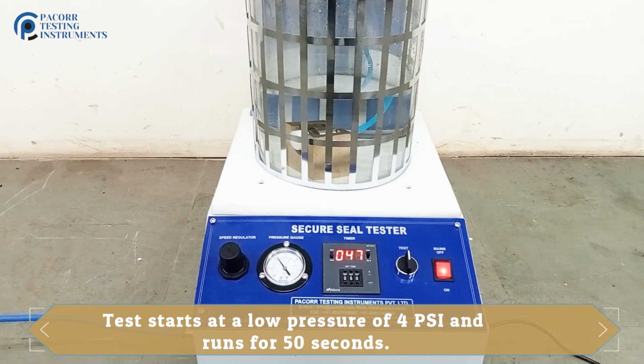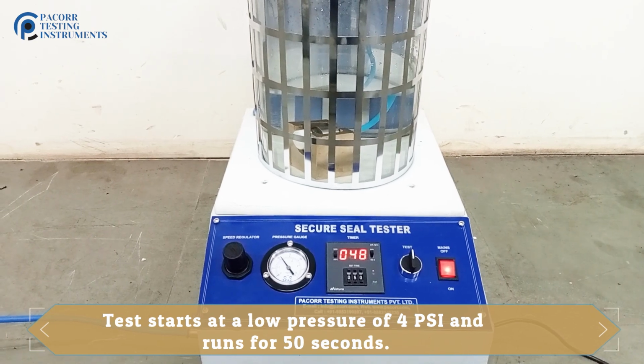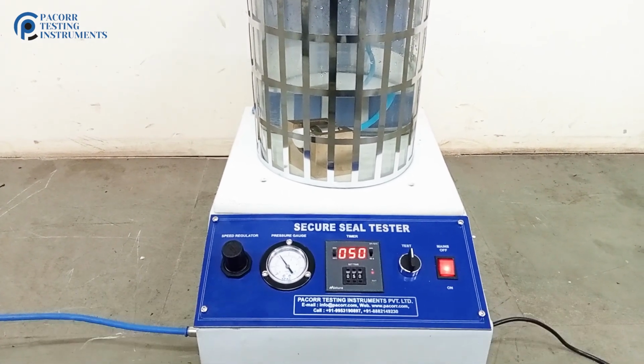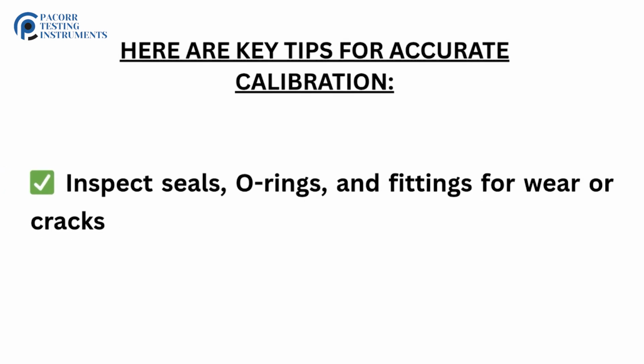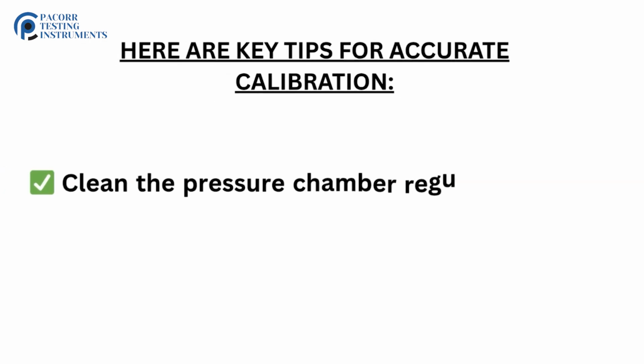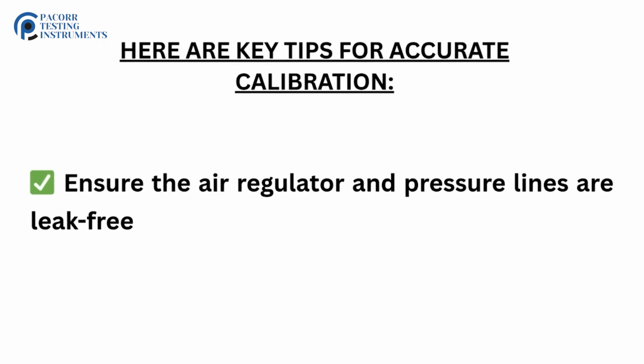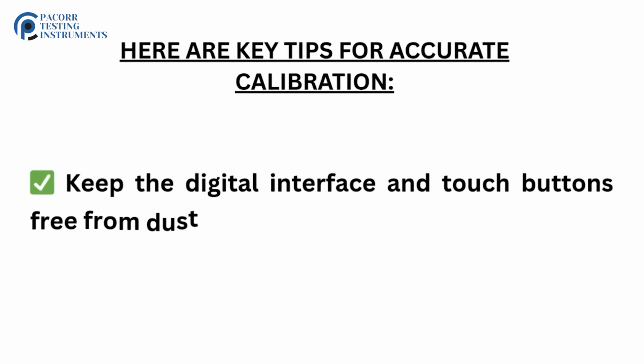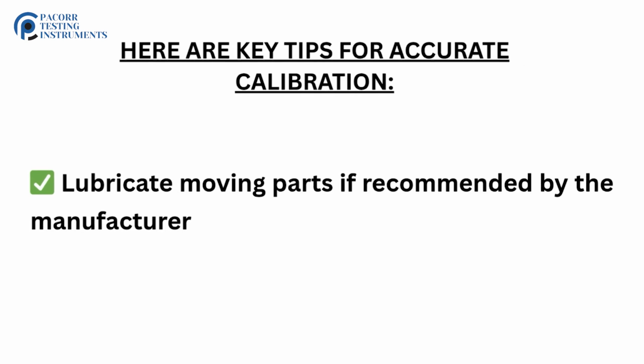Maintenance checklist. Regular maintenance is just as important as calibration. Follow this quick maintenance checklist. Inspect seals, O-rings and fittings for wear or cracks. Clean the pressure chamber regularly to avoid residue buildup. Ensure the air regulator and pressure lines are leak-free. Keep the digital interface and touch buttons free from dust and lubricate moving parts if recommended by the manufacturer.